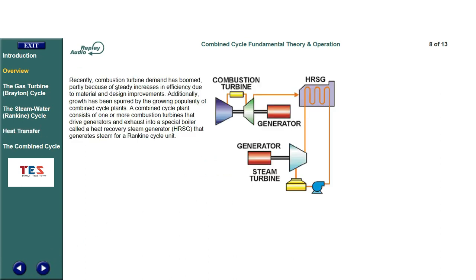Recently, combustion turbine plant demand has boomed, partly because of steady increases in efficiency due to material and design improvements. Additionally, growth has been spurred by the growing popularity of combined cycle plants. A combined cycle plant consists of one or more combustion turbines that drive generators and exhaust into a special boiler called a heat recovery steam generator, or HRSG, that generates steam for a Rankine cycle unit.